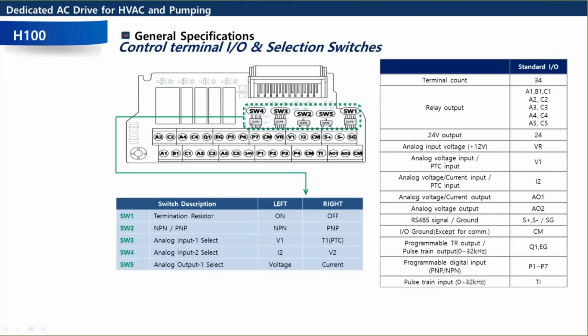So we have 5 of them. We have a termination resistor on there that's built in. So that's termination for like an end-of-line drive on a communication network, like Modbus, for example. We have our PNP NPN switch, so we could switch between sinking and sourcing, essentially. So it's a little bit versatile for the PLC or controller connection. And then we have the 2 analog inputs. We could switch from voltage to PTC, which PTC would be like a temperature feedback from a motor, if you're going to be doing that. So that's a nice option to have standard. Just flip your switch. Then we have I2V2, so that's another switch.